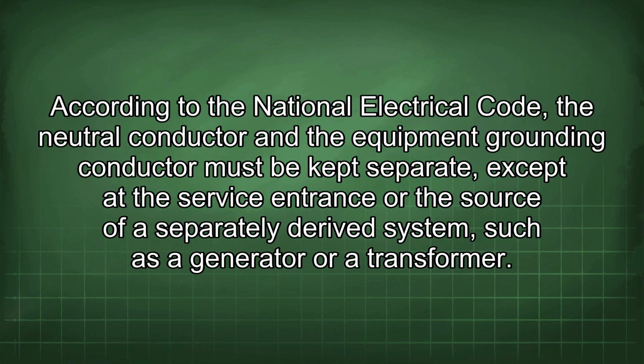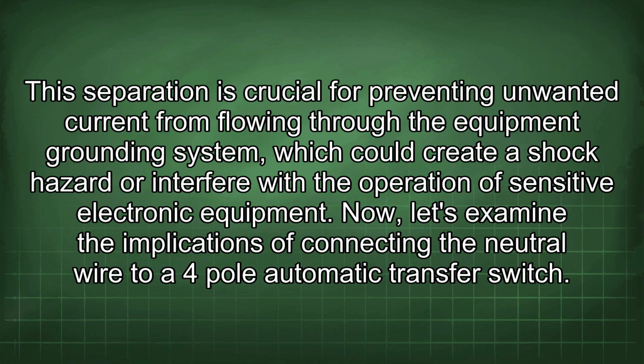According to the National Electrical Code, the neutral conductor and the equipment grounding conductor must be kept separate except at the service entrance or the source of a separately derived system such as a generator or a transformer. This separation is crucial for preventing unwanted current from flowing through the equipment grounding system, which could create a shock hazard or interfere with the operation of sensitive electronic equipment.